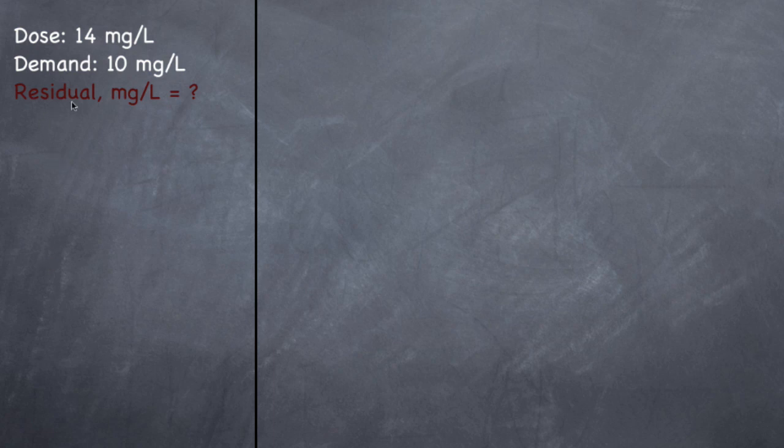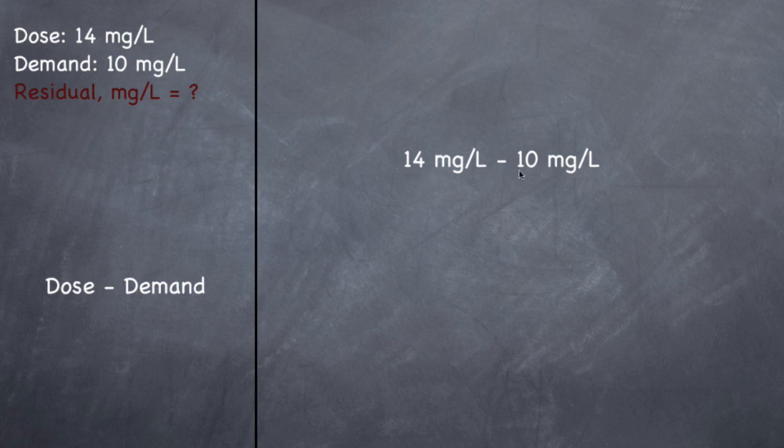Okay, so now we need to find residual. What was left over? We have a dose and we have what is being consumed. So the formula for residual is dose, what we fed, minus the demand, what was consumed, and that'll give you what was left over. So if we go ahead and do that, dose is 14 milligrams per liter, minus 10 milligrams per liter demand, gives you a residual of 4 milligrams per liter. That's how much is left over.